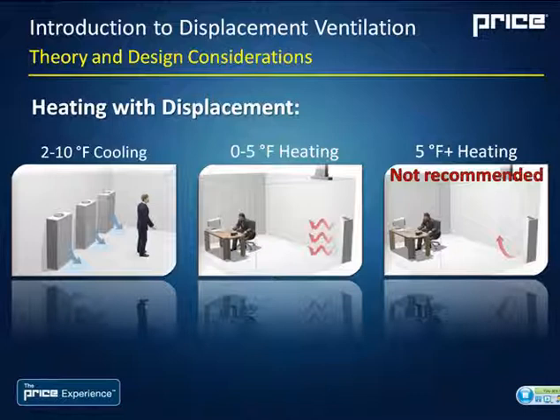Now there's three sort of scenarios with displacement ventilation. The first is the one we've been talking about, where we have a cooling differential, where the supply temperature is significantly cooler than the room temperature, so about 2 to 10 degrees Fahrenheit. In this case, the cool air is more dense than room air, and it's going to sink to the floor and then travel across the floor and find the heat sources.